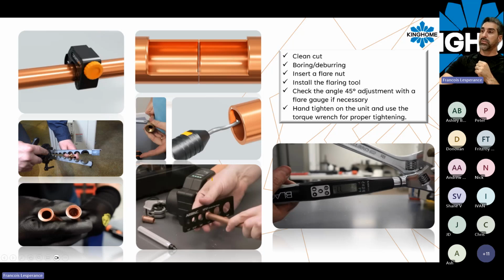The next step is to remove the inside portion of that pipe. Using your reamer, you will need to deburr the inside of it. Make sure you don't have any inner burr here that is blocking or making a bad sealing position on the valve directly. So you need to remove this inner portion when you do a flare connection.